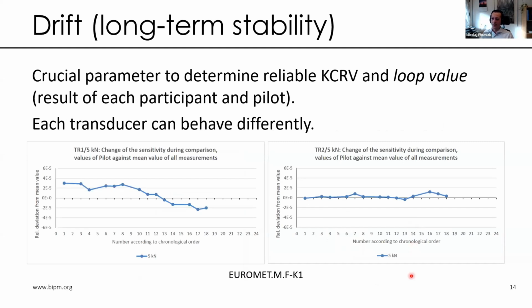When we go to drift or long-term stability, that is actually a crucial parameter in force and torque comparisons. It's very important to analyze this drift very carefully to be able to determine a reliable key comparison reference value, and of course a loop value for each loop. Each transducer, each transfer standard, can behave very differently in different key comparisons.